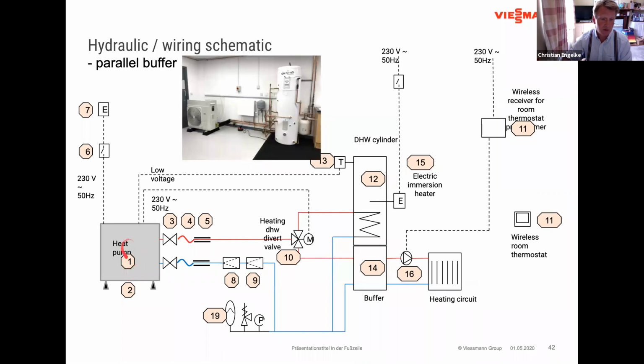We have the outside unit in here, which is this part here, and then the flow and return pipes going into the building and going to a 3-port valve. The 3-port valve is located inside the building and controlled electronically by the heat pump. So one flow pipe goes into the hot water cylinder, which is the top part of this part, and then the other outlet hot water pipe goes to the buffer store.